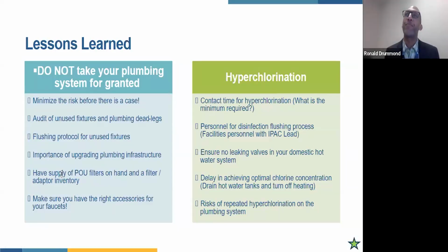During that process, you also want to make sure you don't have any leaking valves. We talked about the importance of temperature and how high temperature water leads to chlorine dissipation. So if you have leaking valves in your hot water system, you might be artificially raising the temperature during that process, and that means it'll take longer to reach that CT time—we know from experience. Drain down your hot water tanks and shut off the heat to your hot water tanks during hyperchlorination. Again, if you don't do that, you'll artificially raise the temperature of your loop, and it'll take longer to reestablish water to the floors.